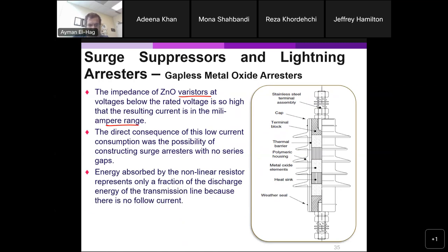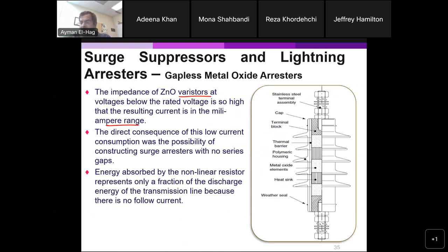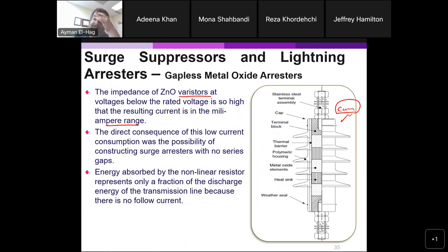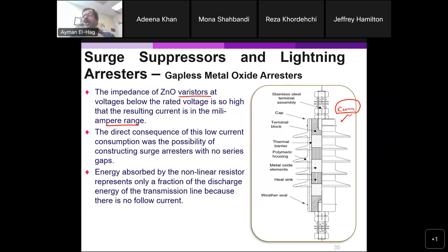The energy dissipated or absorbed is very important because we want to avoid thermal runaway — when temperature keeps increasing, it can cause an explosion of the surge arrestor. This can happen when the material fails thermally. The housing material used to be ceramic. However, imagine an explosion inside ceramic — it becomes like shrapnel, which is very dangerous. The recent trend is to use silicon rubber housing. If an explosion happens, the rubber just absorbs the energy without causing harm to surroundings.